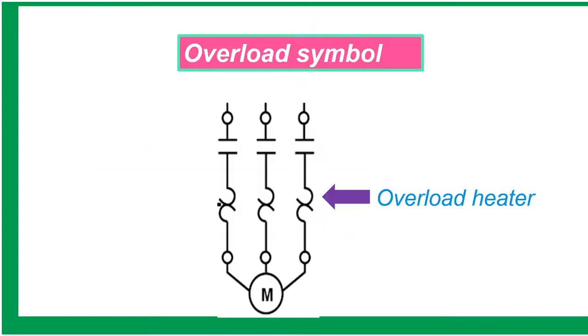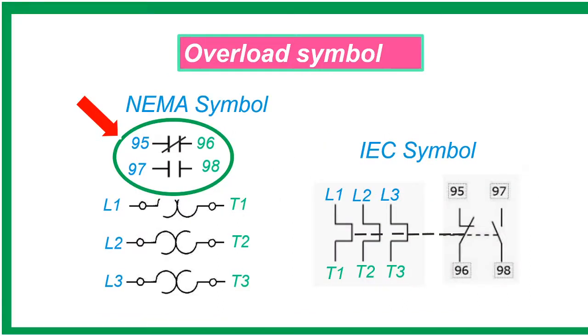The overload heater elements are connected in series with a contactor to protect the motor. An overload relay also includes one or more normally open and normally closed contacts. These contacts are connected to pilot buzzer or alarm light for indication to warn the operator or maintenance.